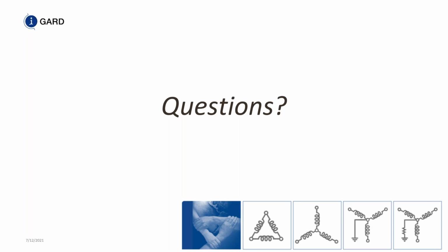Okay, thank you. Next question is, can you please explain the difference between system requirements for US versus Canada? If you look at the NEC, section 250.36 is basically high resistance grounding systems for systems up to 1000 volts. And 250.187 is for systems above 1000 volts. And it gets a little confusing in the US because NFPA 70E says that you can have a system up to 5 kV, 4160 volts. If you limit the fault current to 10 amps or less, you have an arc flash mitigation technique. And then you have the NEC that backs it up, but only for a portion of that voltage.